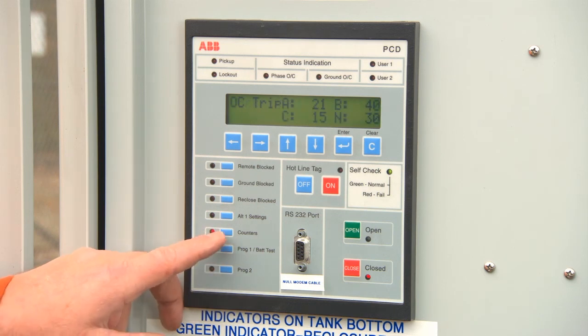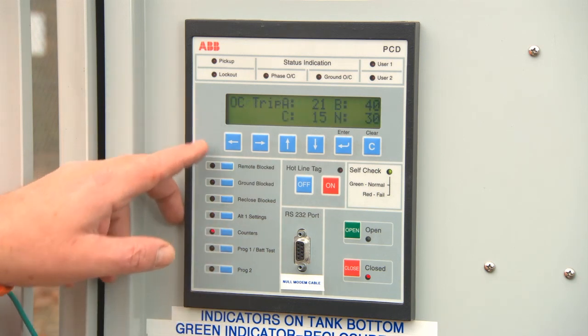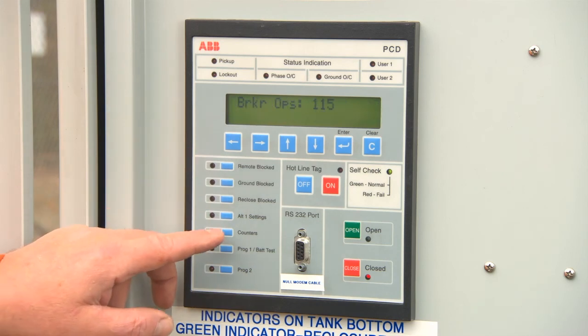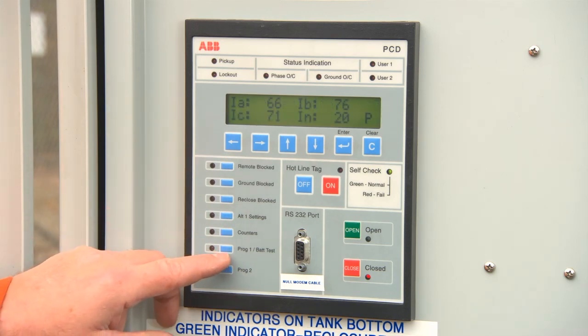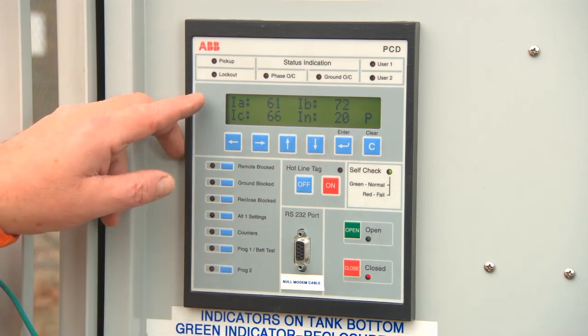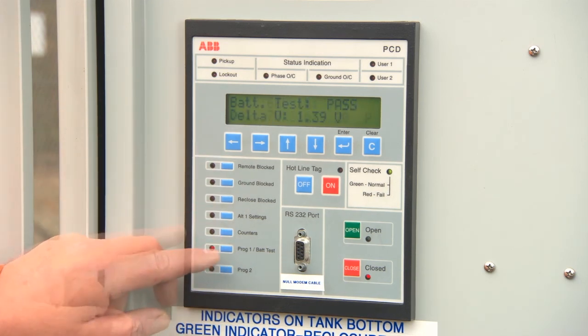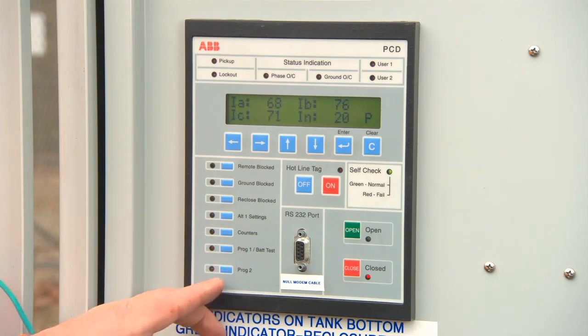Counters. Pressing this button will display the total number of operations performed by this recloser and each individual number of trips per phase. The display will then return to the default screen. Battery test. Pressing this button will perform a battery test, and it gives you its functionality. Program 2. This is typically not programmed. However, it is possible to set a different metering scale if desired.